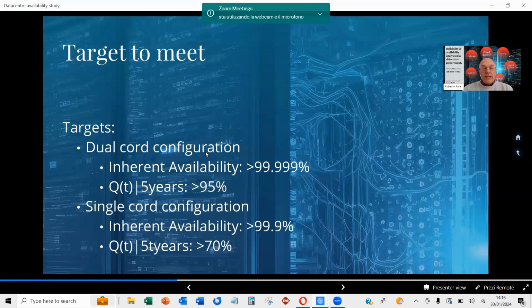We didn't actually use inherent availability, because inherent availability holds on the hypothesis that your system has reached a mature, steady state condition. Looking at the numbers we were inputting for circuit breakers, UPS, transformers, isolating transformers and so on, it was quite clear we were going well beyond the 5 years, or certainly we wouldn't have a stable system.